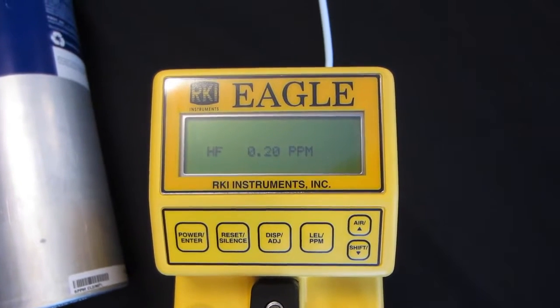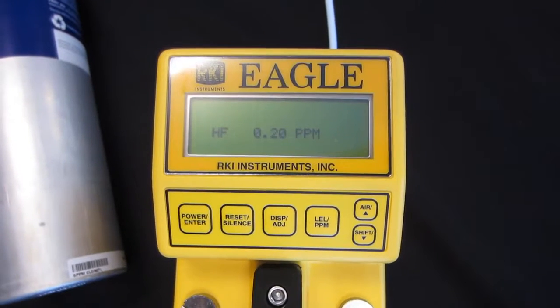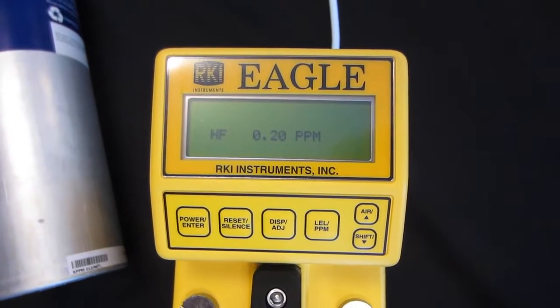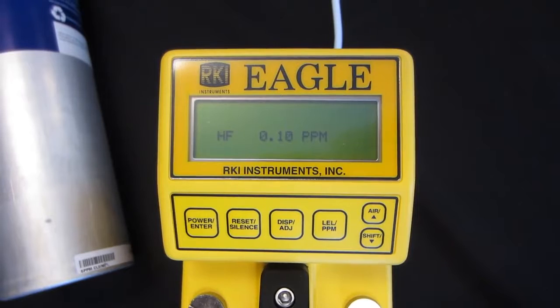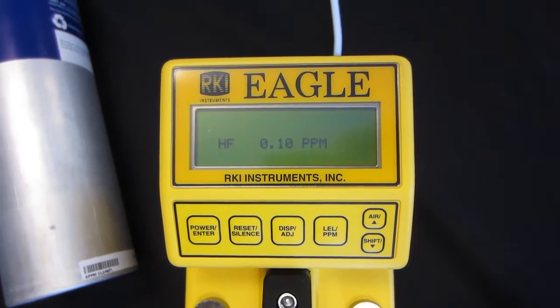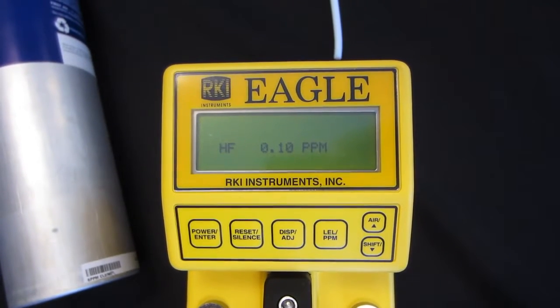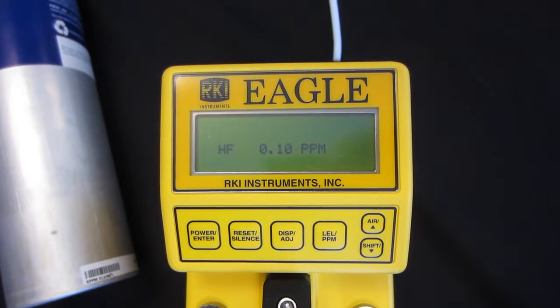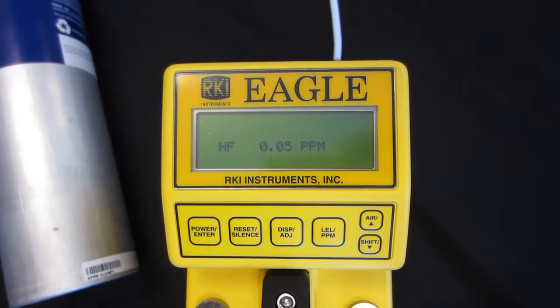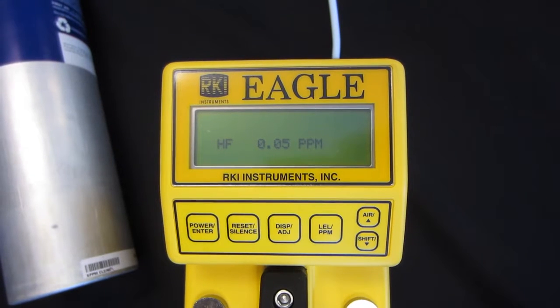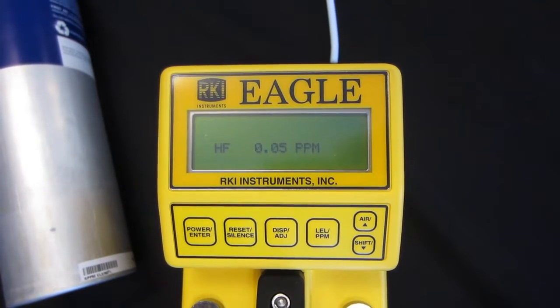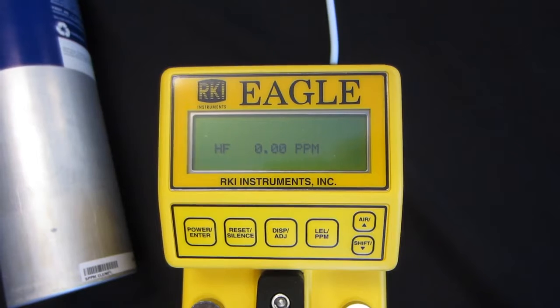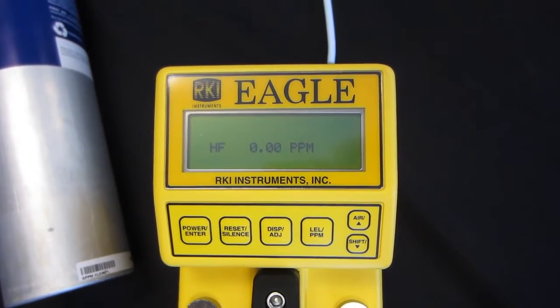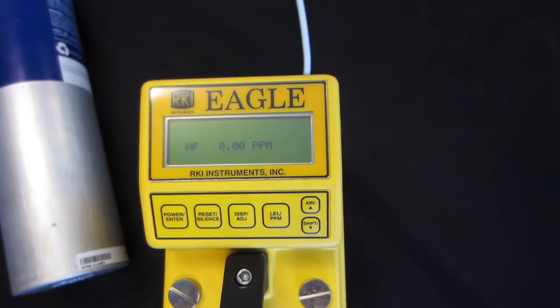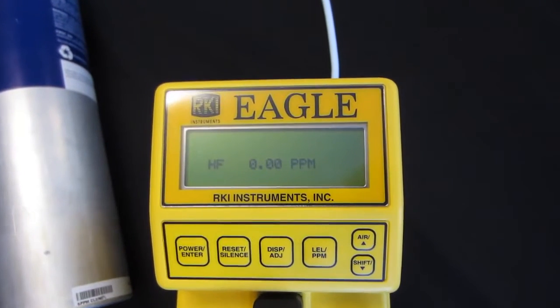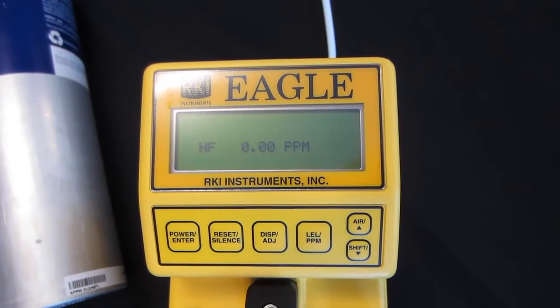You don't want to make the plus or minus parameter too close to the cal value, because otherwise you're kind of defeating the purpose of the bump test. If you're going to get too close to the cal value, you might as well just calibrate the instrument in full at that point. And the reading is still dropping. We're just about to 0, 0.05. There we are. Now we're at 0. And that concludes the example of bump testing the Eagle.